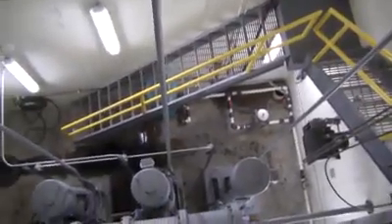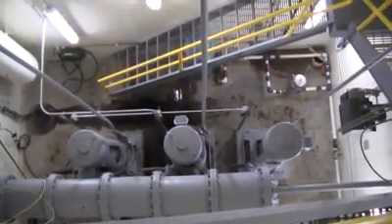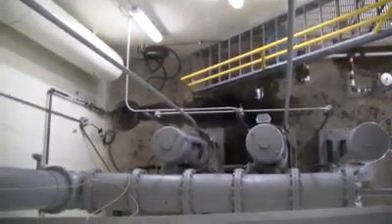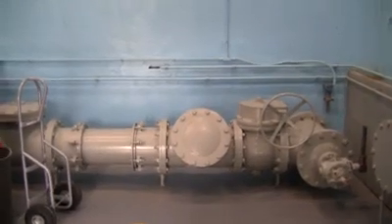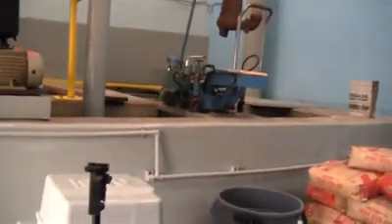These are the lift station pumps, and they pump the raw sewage up into the equalization basin, where we control how much sewage actually goes to the treatment plant. This blue wall is an equalization basin. Here we store the wastewater. It's 349,000 gallons. From this point, we can regulate what goes into this grit tank, and that's where we remove inorganic material: rocks, sand, gravel, eggshells.